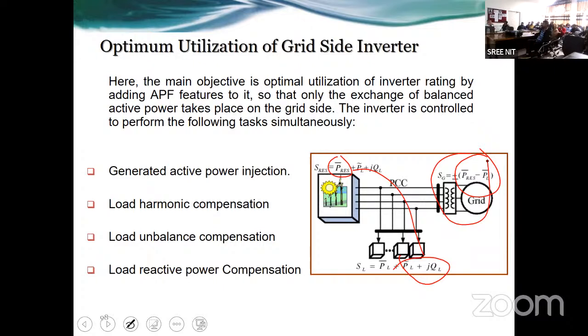So here the main objective is the optimal utilization of inverter rating by adding active power filter features to it, so that only the exchange of balanced active power takes place on the grid side. The inverter is controlled to perform the following tasks simultaneously: generated active power injection, PRES, load harmonic compensation, that is PL oscillatory part, and load unbalanced compensation, that means whole reactive power demand of the load, and load reactive power compensation also, unbalance also. All those four parts I have built within the same converter.